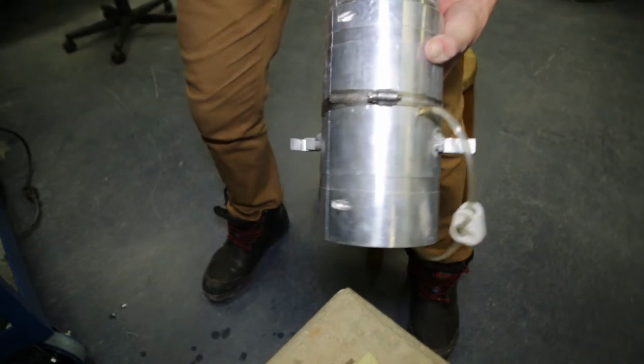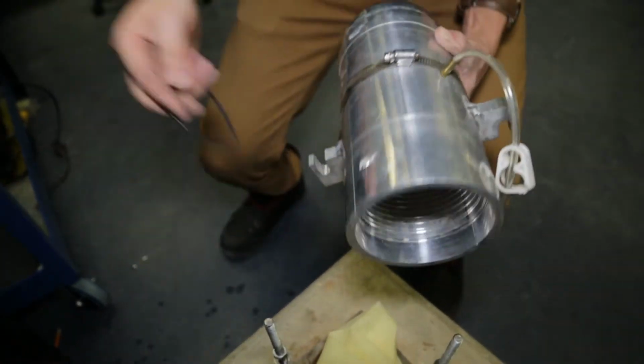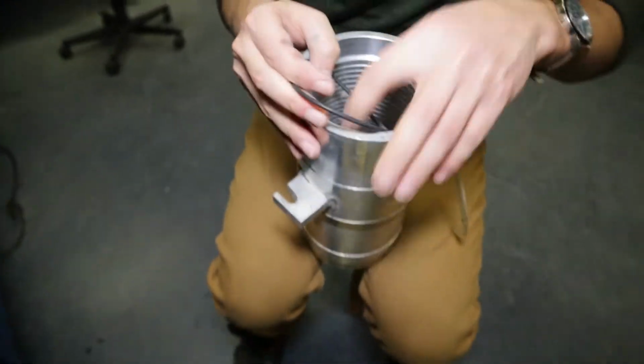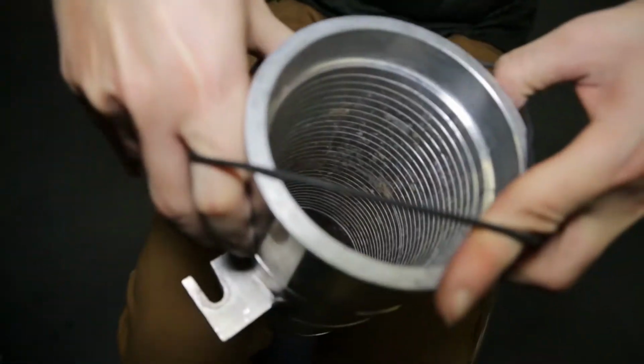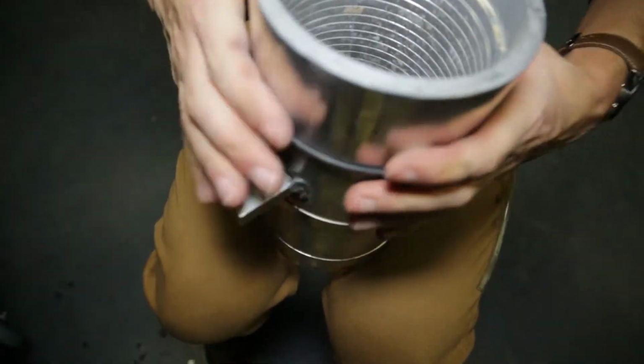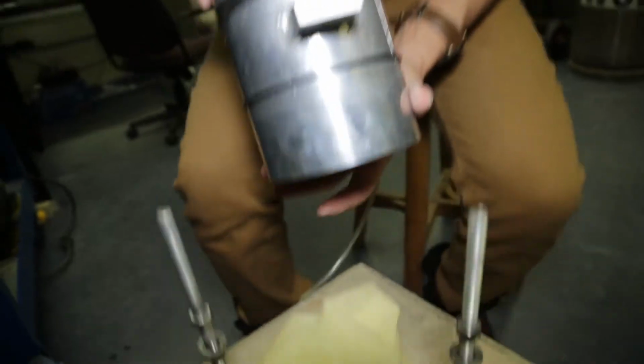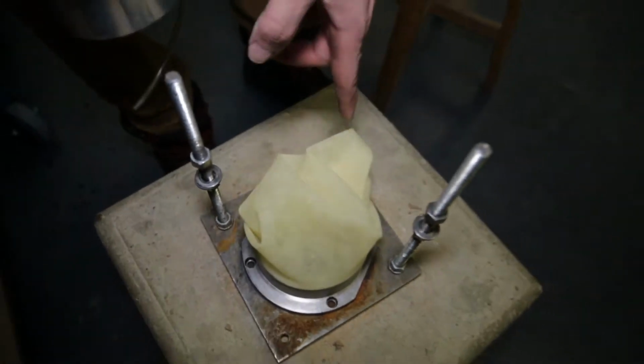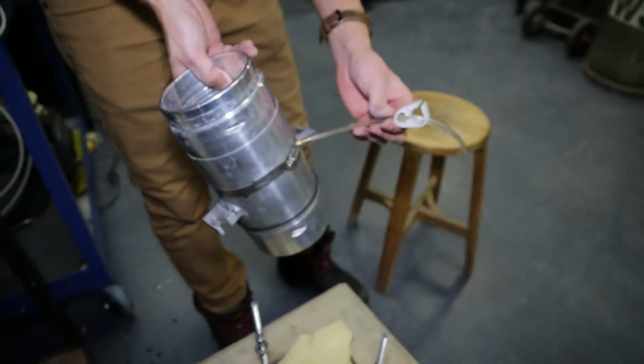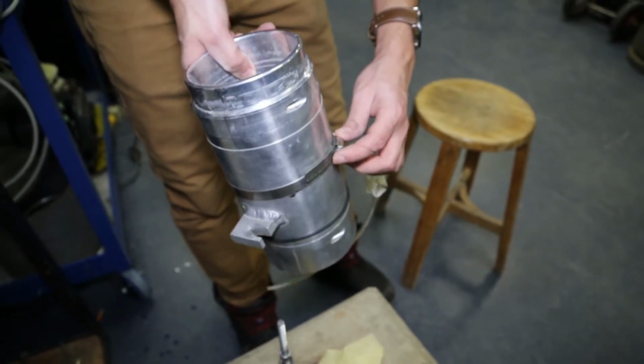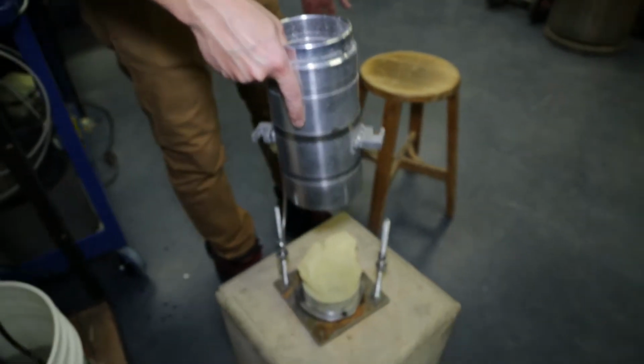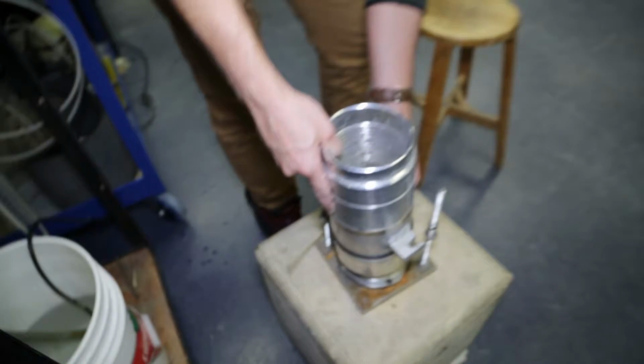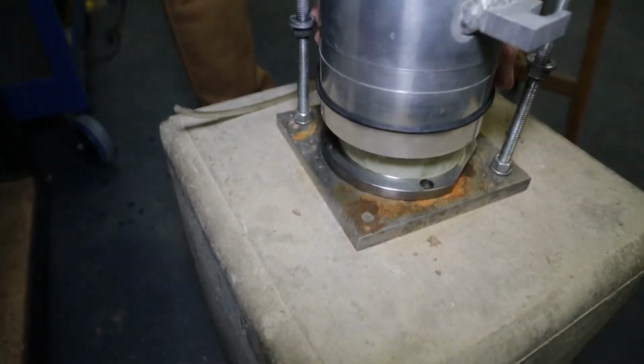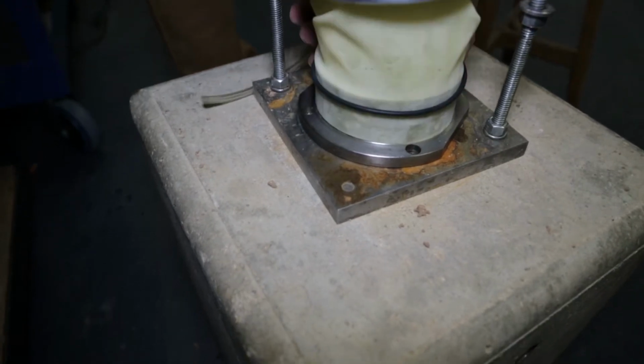Close it. And then apply the O-ring. This O-ring is going to hold the membrane to the base plate. Also notice that the orifice is on this side, so the suction hose and the nut here are supposed to be facing the same direction. I'm gonna slide it here and lower the O-ring. It's just gonna snap on the membrane.